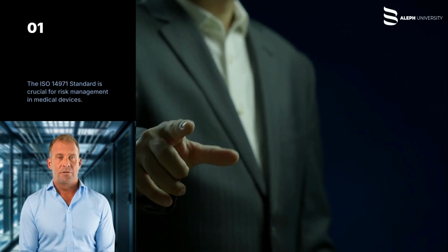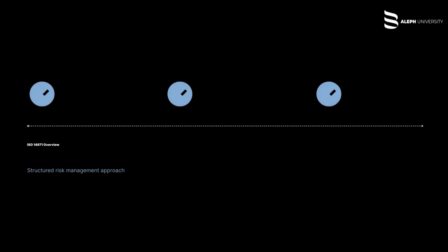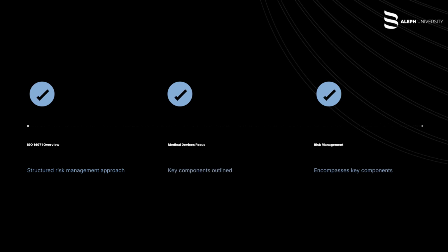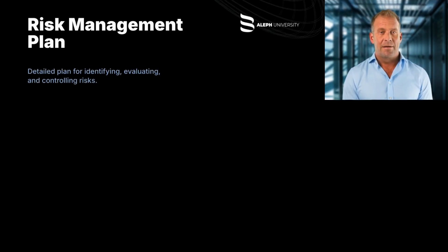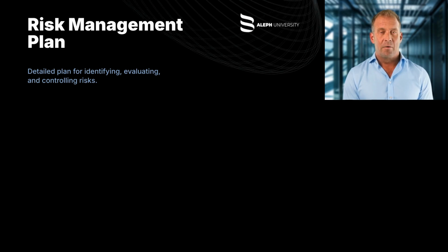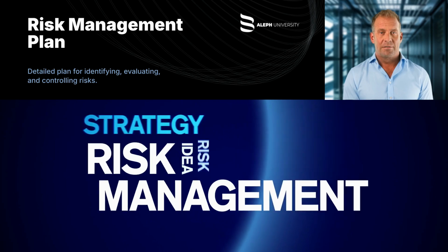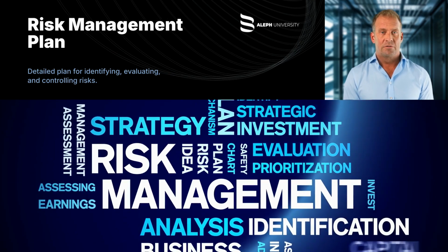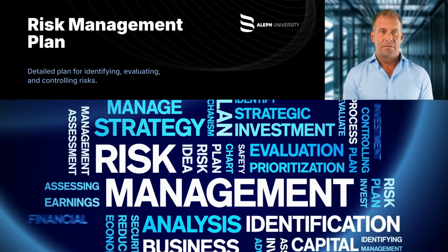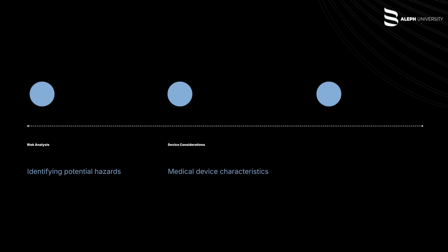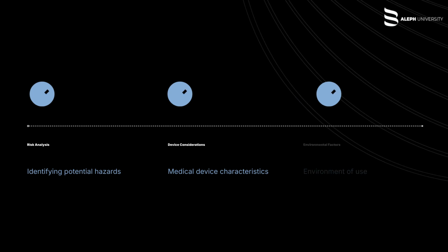The ISO 14971 standard. ISO 14971 outlines a structured approach to risk management for medical devices, encompassing the following key components. Risk management plan, developing a detailed plan that outlines the process for identifying, evaluating, and controlling risks throughout the device's lifecycle. This plan should define roles, responsibilities, and criteria for risk acceptability. Risk analysis, systematically identifying potential hazards associated with the medical device, considering its intended use, characteristics, and the environment in which it will be used.